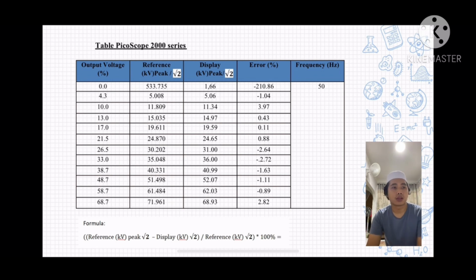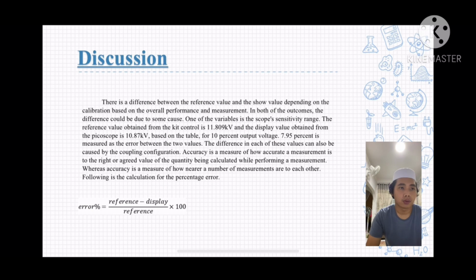Okay, for the discussion: after we finished this lab 3, we found that there is a difference between the reference value and the shown value, depending on the calibration based on the overall performance and measurement. In both outputs, the difference could be due to some causes, one of the variables being the scope sensitivity range. The reference value obtained from the kit control is 11.809 kilovolt and the display value obtained from the picoscope is 10.87 kilovolt, based on the table we obtained. For 10% output voltage, 7.95% is measured as the error between the two values.